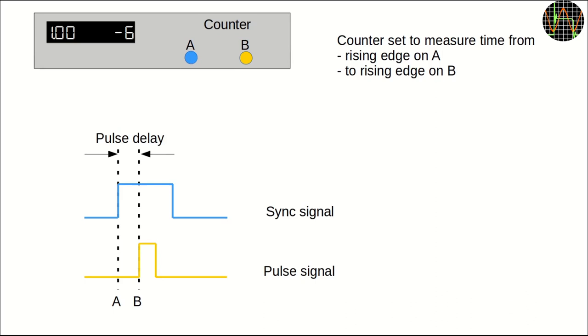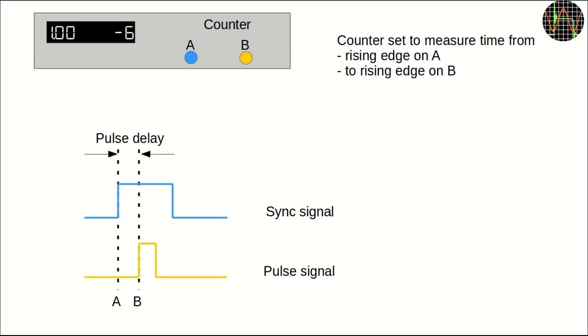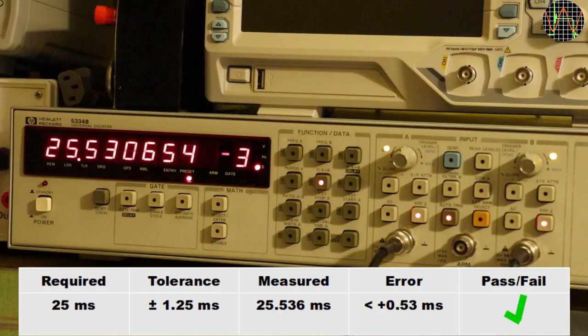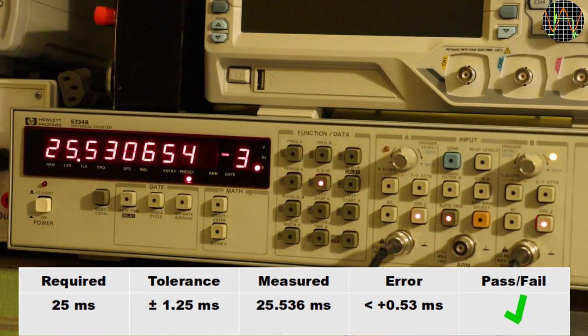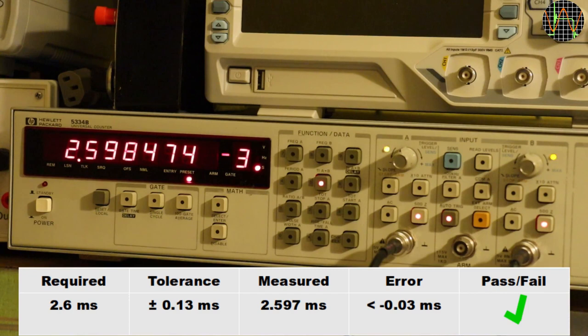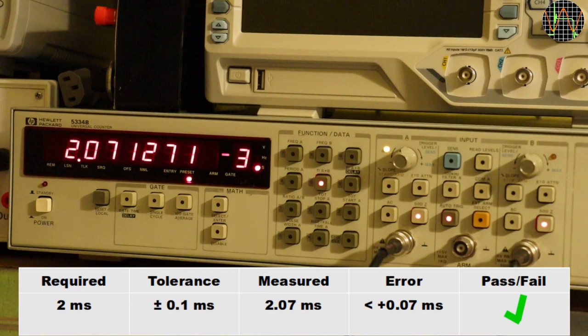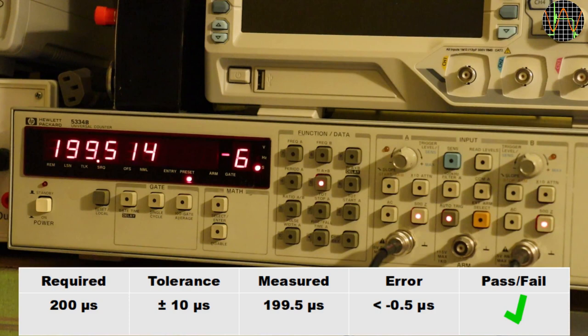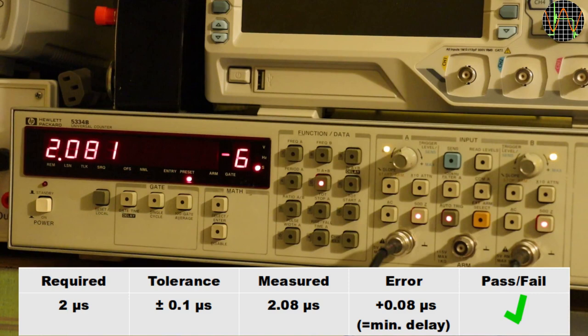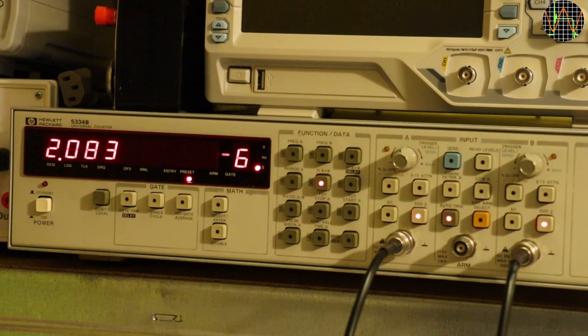All tests use the same 100 ns pulse width but need tedious settings of delay and period value pairs for each test which I skip showing. We start with a delay of 25 ms with an allowed tolerance of ±1.25 ms. 2.6 ms next with a tolerance of 0.13 ms. 2 ms with a tolerance of 0.1 ms. 200 µs with a tolerance of 10 µs. 20 ms with a tolerance of 1 ms. 2 ms with a tolerance of 0.1 ms. And we are still in spec with 0.08 µs off and we know that these 80 ns are basically the unavoidable sync delay I showed earlier. In total, pulse delay works within the allowed tolerances.